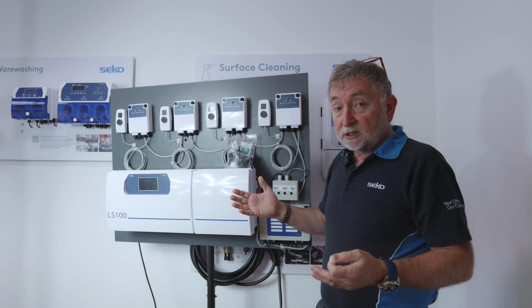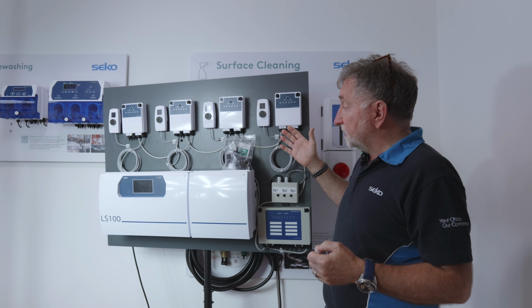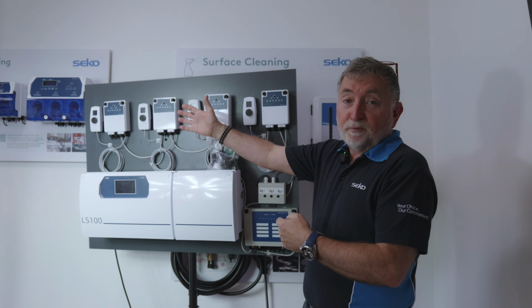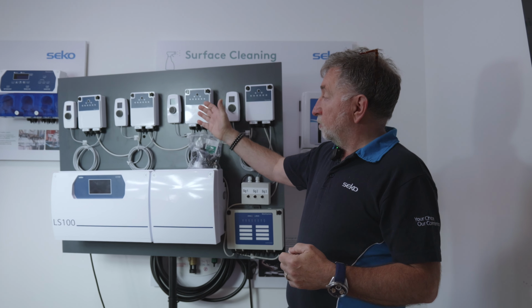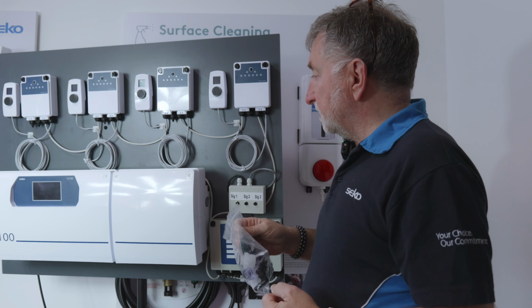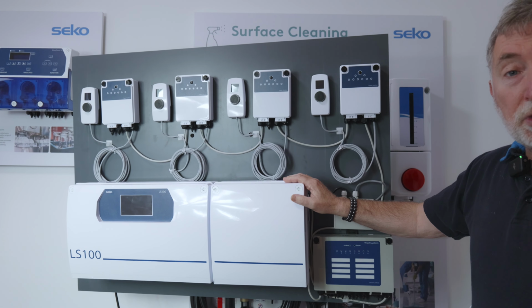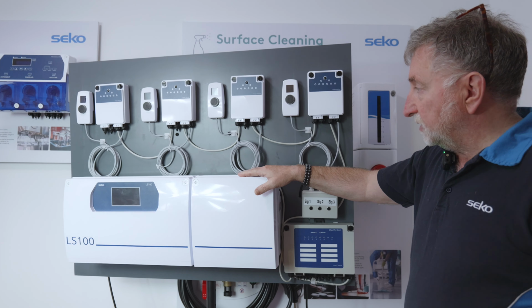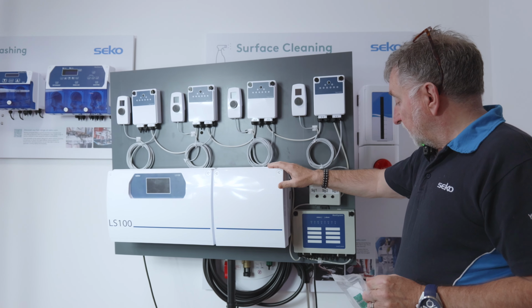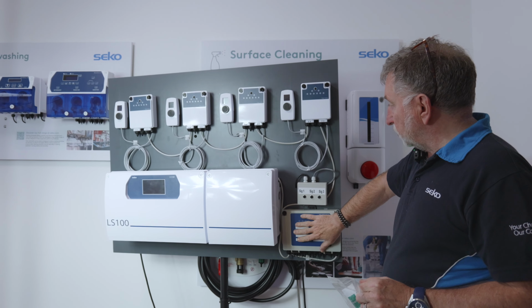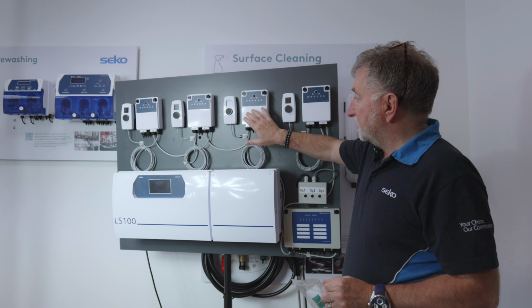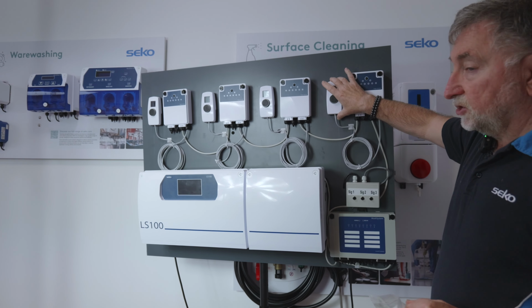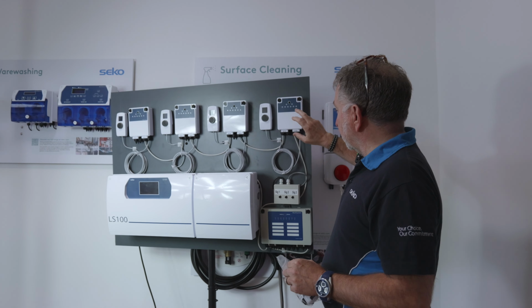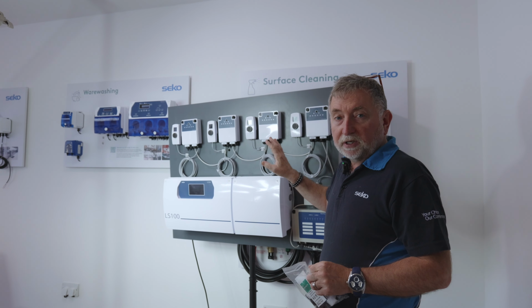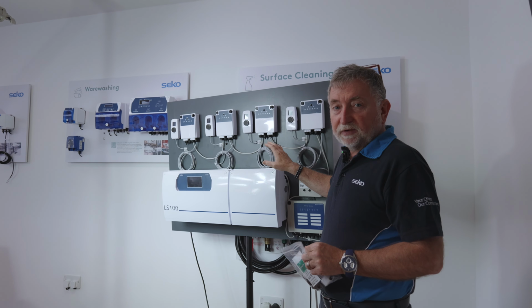So let's have a look at a typical system. This is set up now for 4 washer extractors. Obviously for the point of this video we've laid it out on one panel, but these items can be placed in any suitable position in the laundry. Just to run through the system, we have one CAN bus 4-core cable which links all of the elements on the system, as we call the peripherals. So in this case it would be a low-level alarm module going up to your signal interfaces, and then with the addition of the optional formula selectors which plug directly into the signal interfaces, and we'll be looking at the signals and the connections a little bit later in the video.